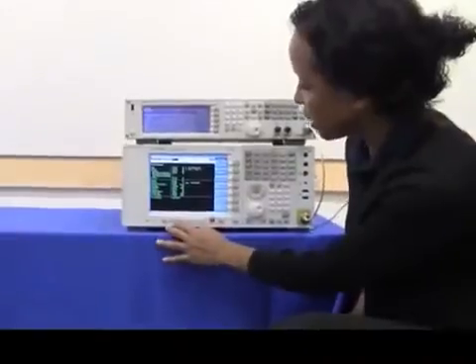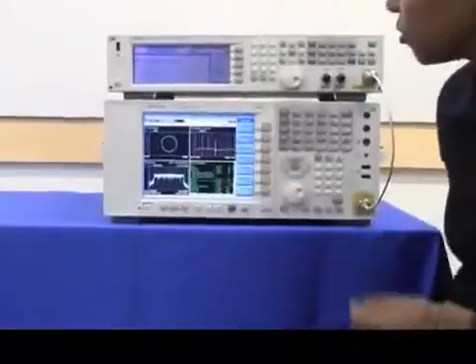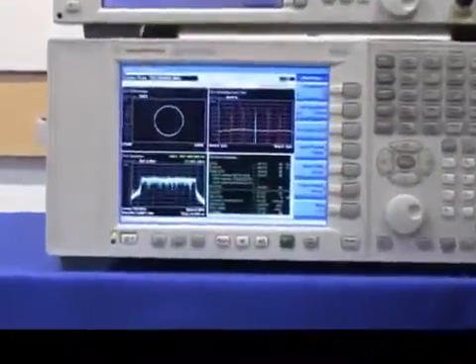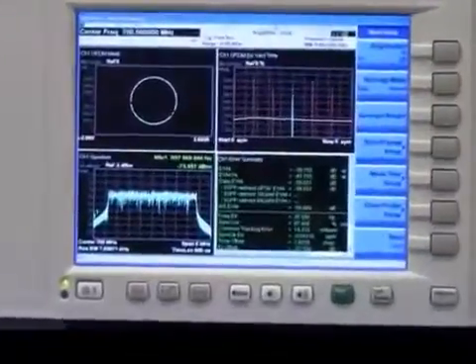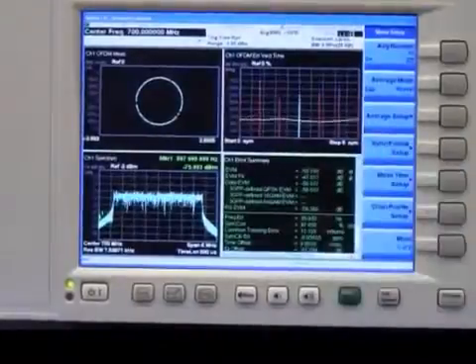I'm going to zoom out of the error summary trace and go back to the default trace, which is showing you four different traces, including the constellation diagram. Here, we're looking at EVM across different symbols, spectrum, and then the error summary.